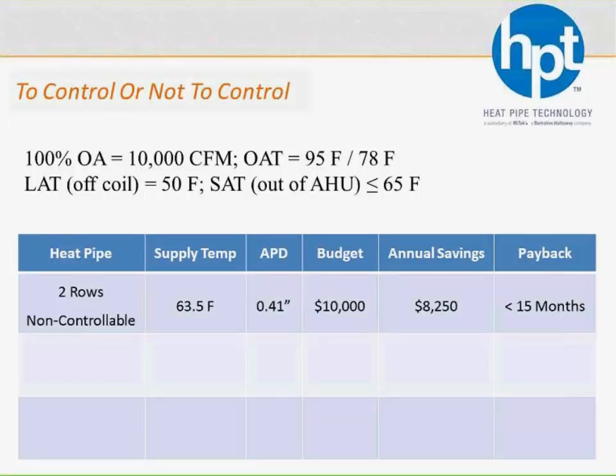Well, one thing you can simply do is just use a 2-row non-controllable heat pipe. At 95 degrees and 50 degrees off the coil, the most reheat you're going to do is 13.5 degrees, so you're never hitting that 65 degrees. It's never going to get too hot. When you factor in the static pressure hit using typical utility rates, I would budget this at about $1 a CFM, so let's just say it's $10,000. And let's say you're going to save on both the pre-cool and the reheat, accounting for the fan penalty, about $8,200 a year. That payback's just over a year, which is pretty common.